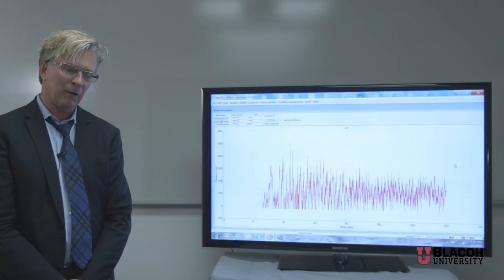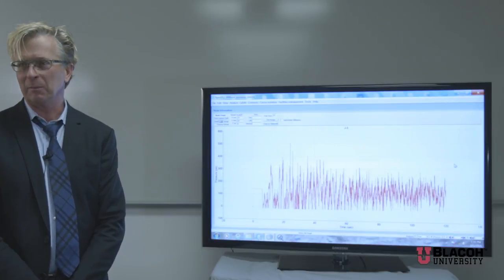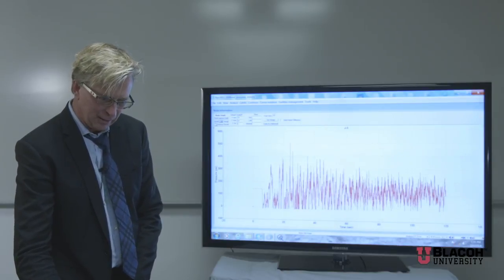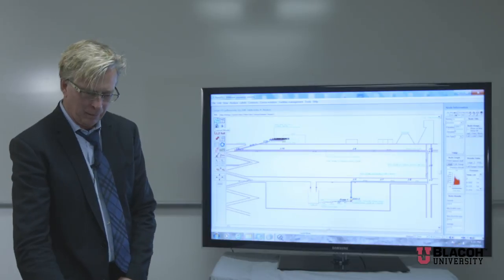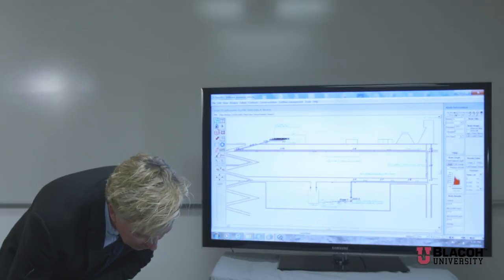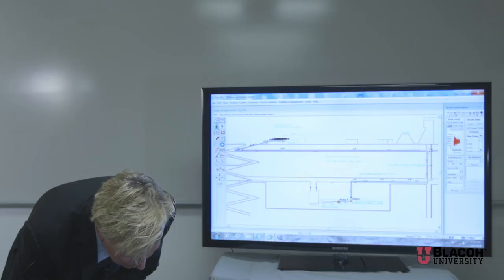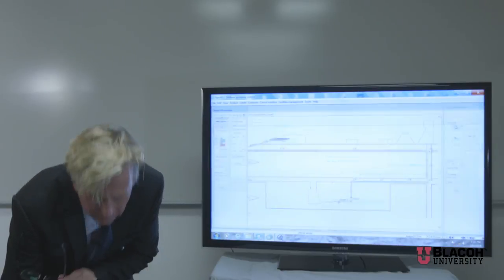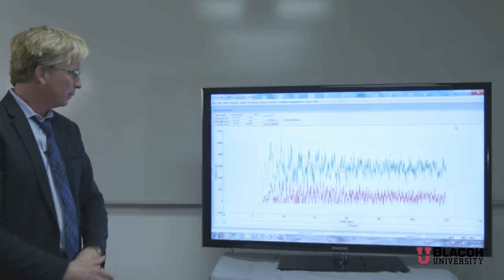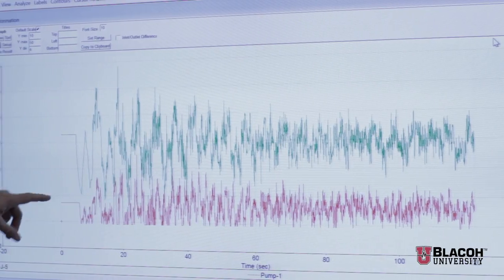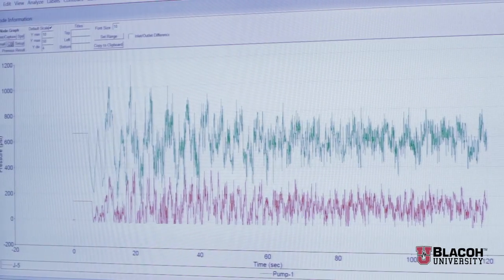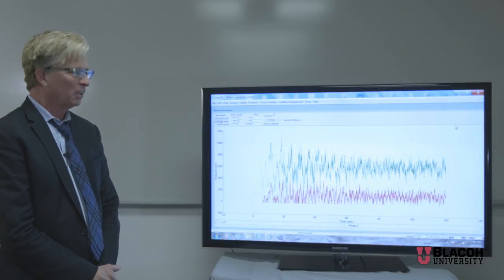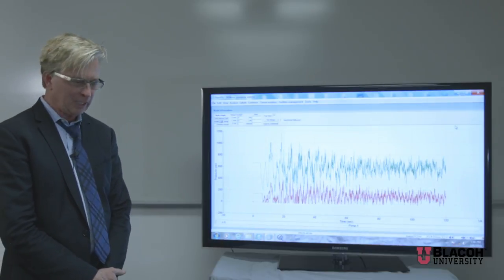You see the oscillation movement of the pipe. I don't think I'd want to be in that tunnel when they turned off the pump. A neat thing about the modeling software is that you can compare the difference between the pump pressure and almost the top of the piping system. We can compare those two pressure graphs during both time steps. We can see the pressure difference and the head loss in the system, but you see the cause and effect of your overall piping system is quite detrimental.